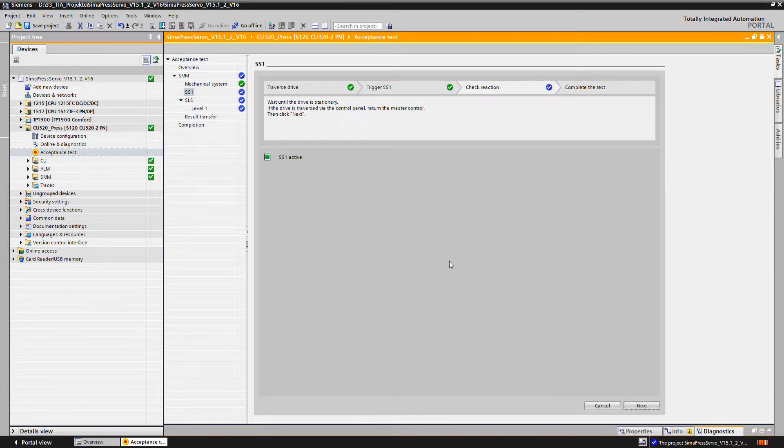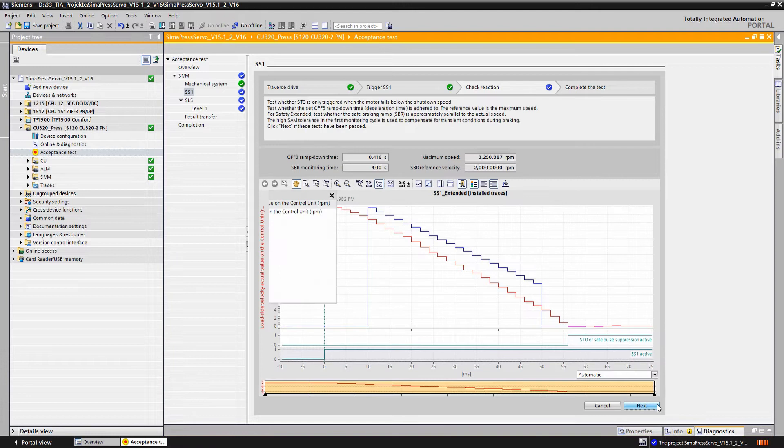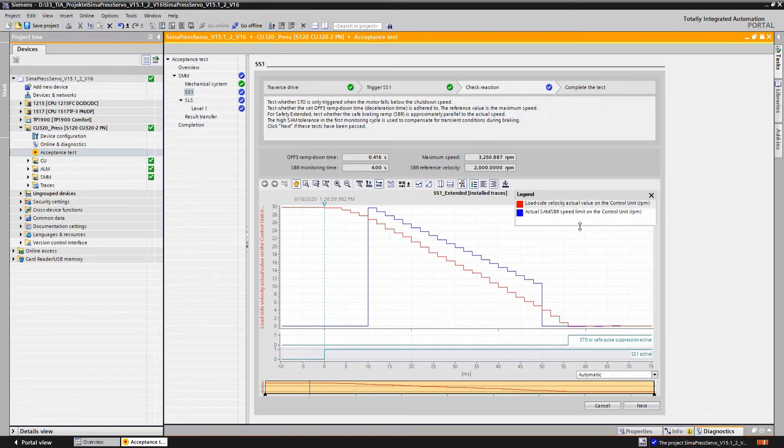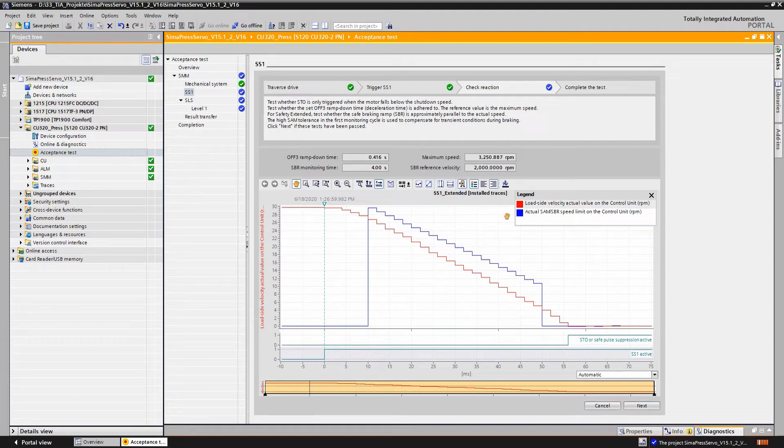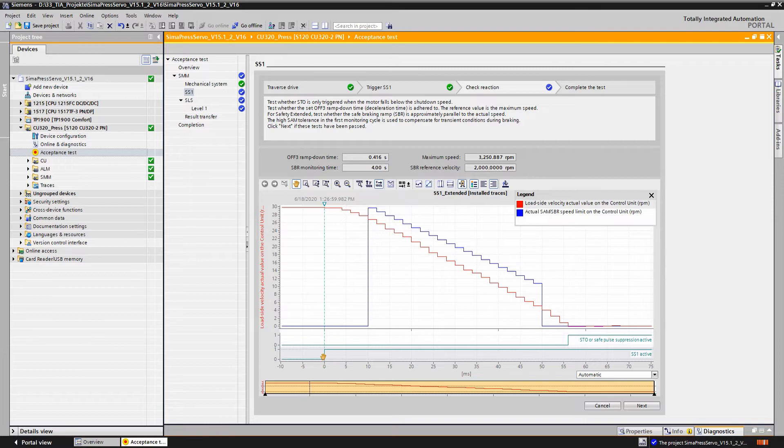Now for the most important part of the test, namely the trace analysis. We check that SS1 trips after the emergency stop command device is pressed, that the speed curve shown here in red corresponds to the braking ramp defined in the specification and that it's not interrupted prematurely.